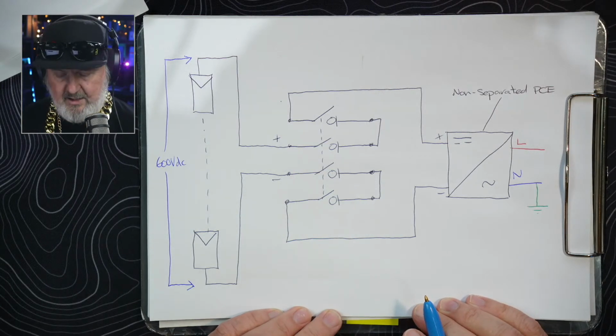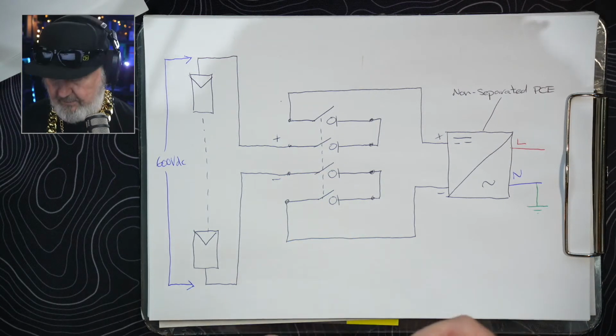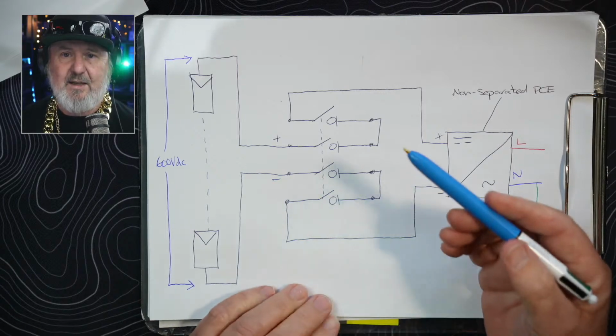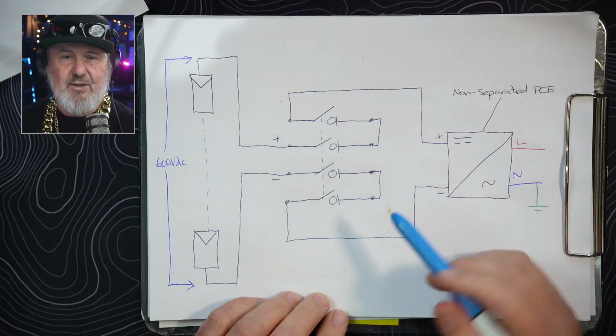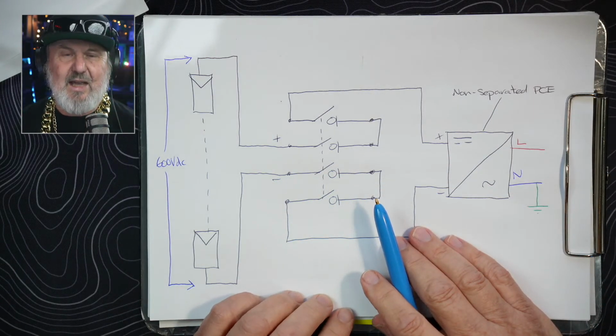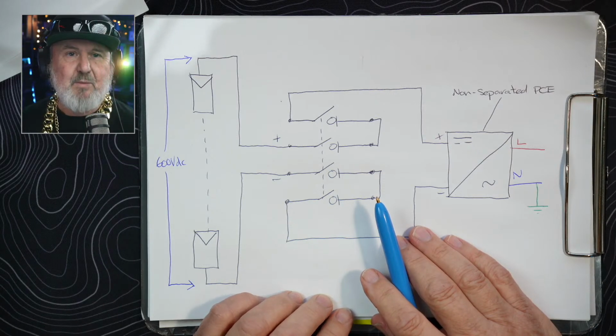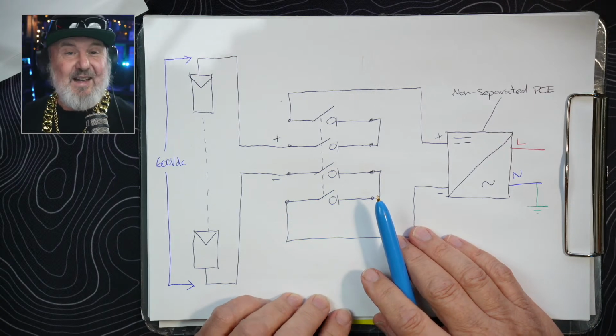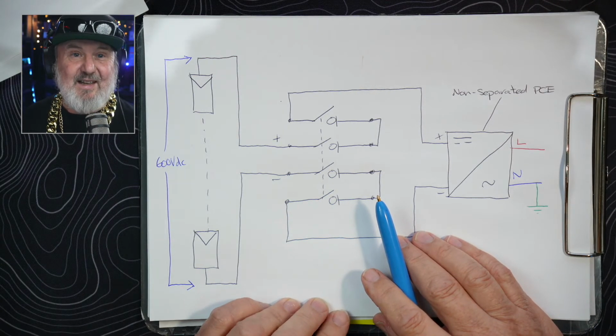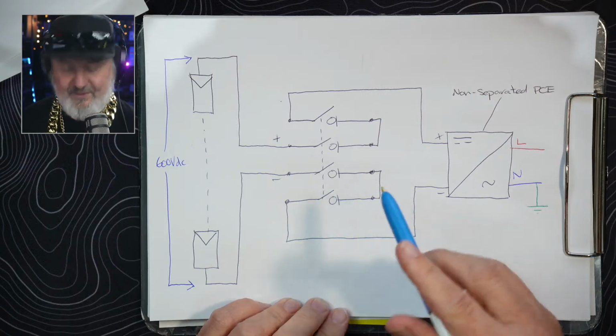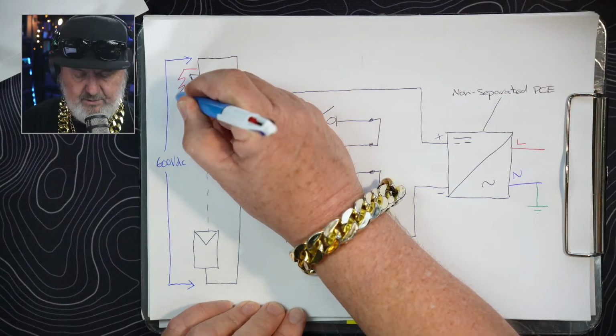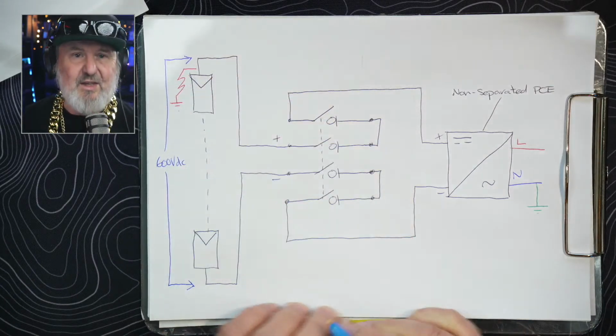Now, the problem comes when we have a fault. Now, I'll get my red fault pen out here. Not unusual to find that cables are damaged, whether it's by poor installation, by lack of maintenance, by one of those lovely Australian possums chewing your cables, or something else, and we end up with a short to earth.